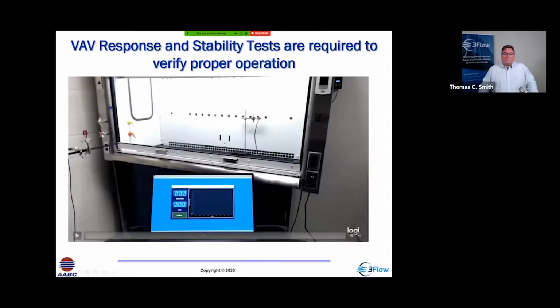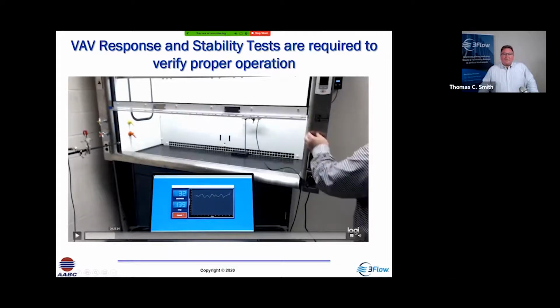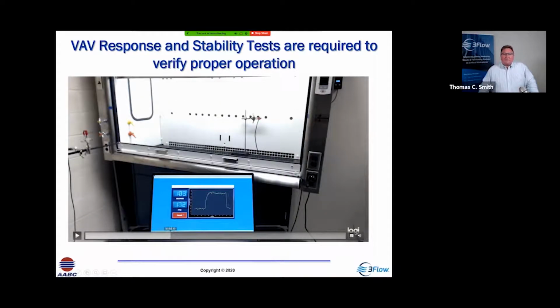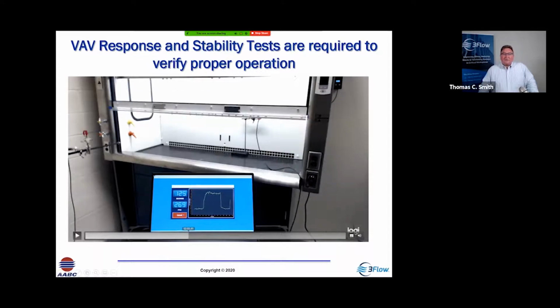So here's an example. We'll show a little video here. As we're recording the data, we've got the sash closed, we've got our probe in the baffle slot, and we're watching the velocity. I'll just move it over here a little bit until we open the sash, and now we see the flow increasing to where it's coming up to a value. And then we go through 3 cycles of this. We're going to close the sash, and when we close the sash, we'll see the flow go down, and 3 cycles of opening and closing.